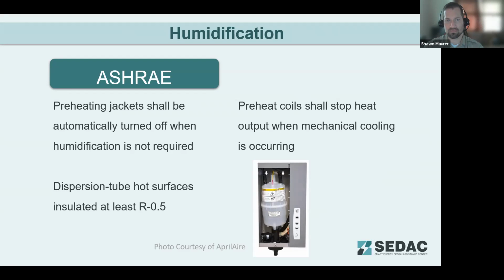Something else that ASHRAE takes into consideration for humidification systems. Some of these systems have preheating jackets that preheat the water going into the humidifier. When it's not required, those preheat jackets should be turned off. Kind of seems like an obvious requirement, but you'd be surprised how many times those things get missed. Preheat coils should stop heat output when mechanical cooling is occurring. Those preheating coils are warming up the air enough that as you're spraying humidifying content into the air, it can readily evaporate, so it doesn't have a risk of condensing on duct surfaces.